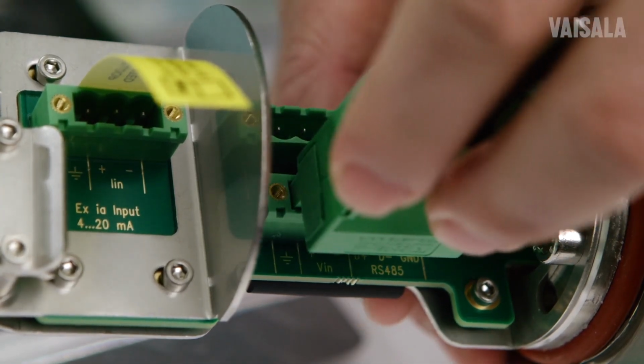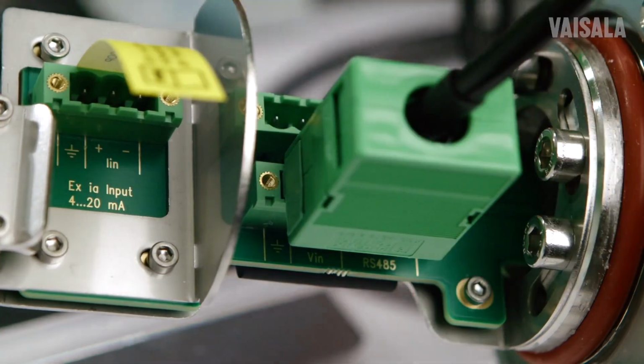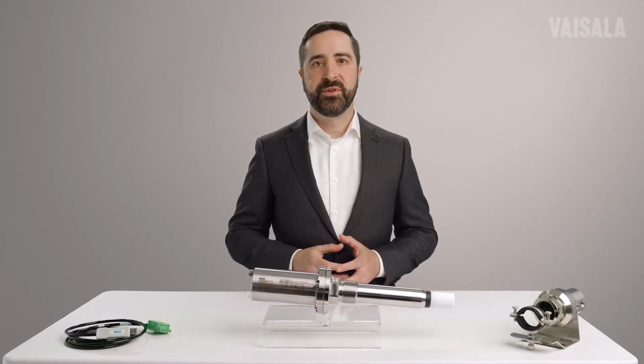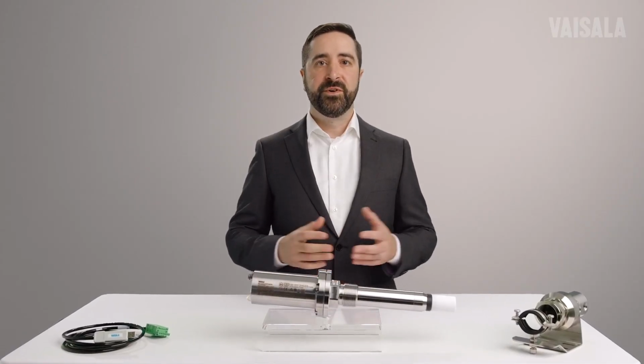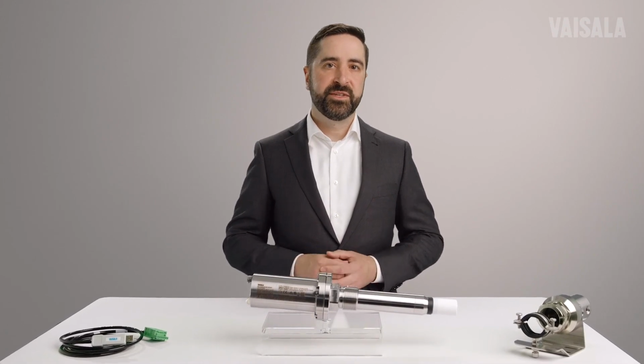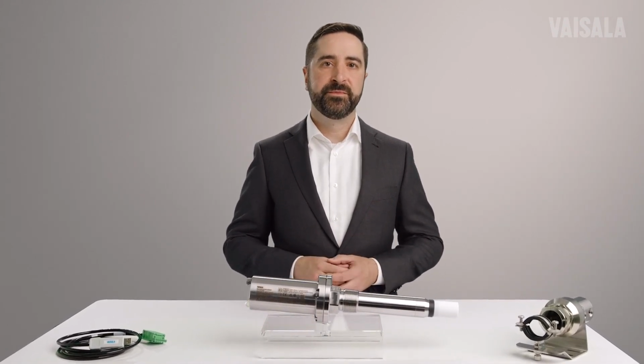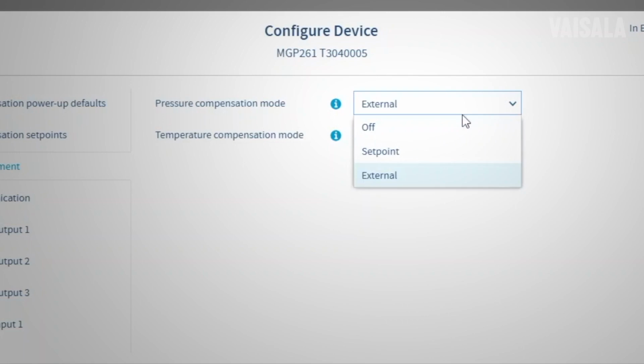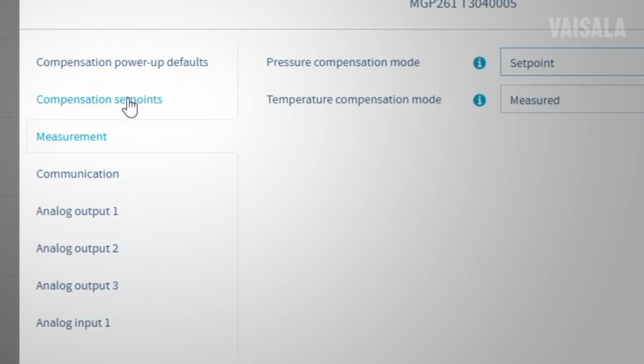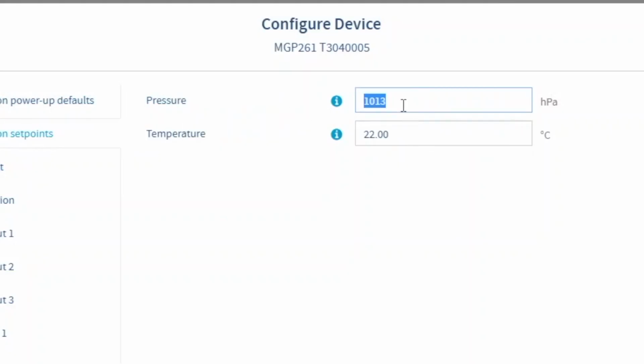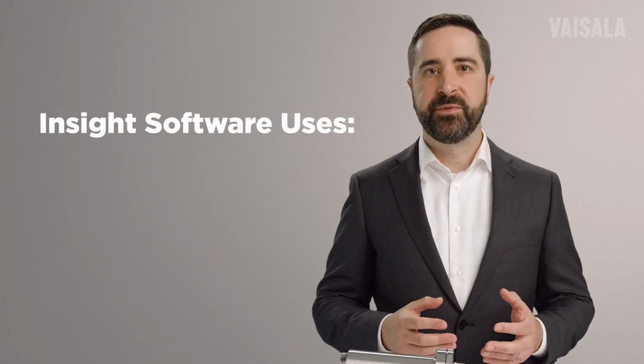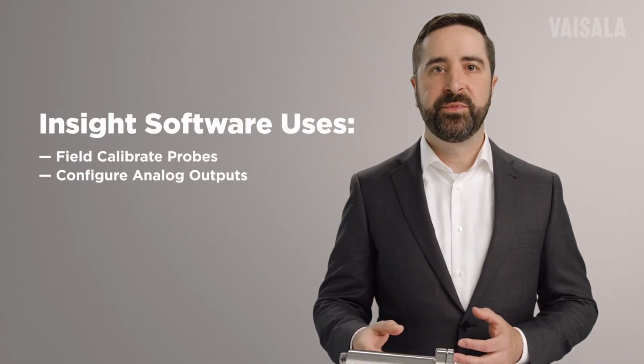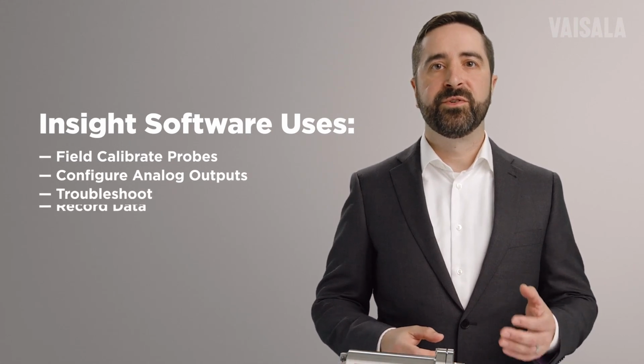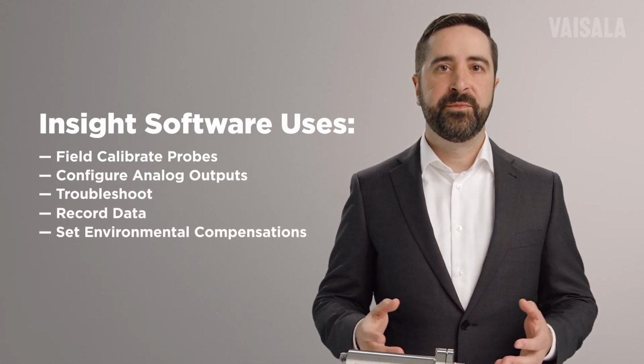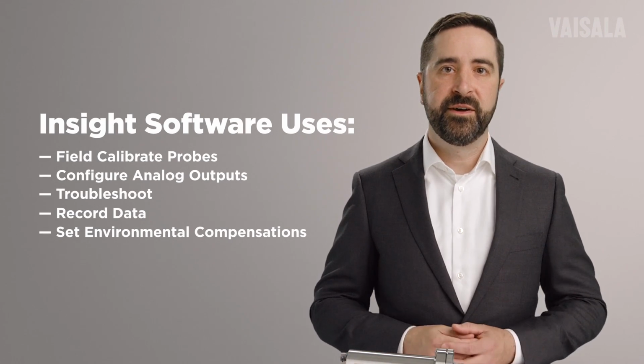That brings me to the other pressure compensation option, which is for processes with a stable operating pressure. For those installations, a fixed pressure setting can be programmed into the probe. This programming is simple and intuitive with our Insight software, which can be downloaded for free from our website. The Insight software can be used to field calibrate the probes, configure the analog outputs for troubleshooting, recording data, or setting the environmental compensations like we're discussing now.